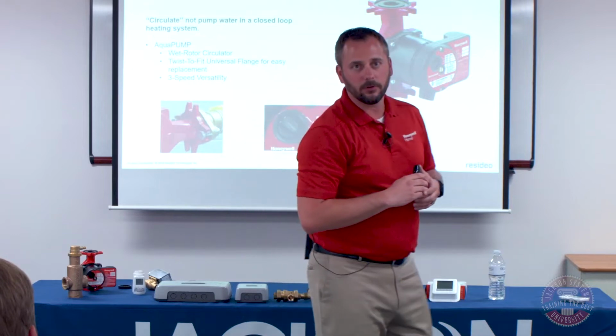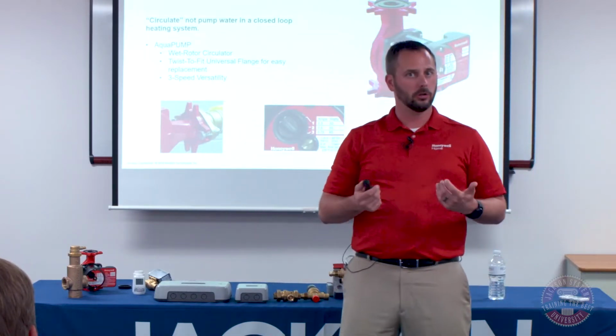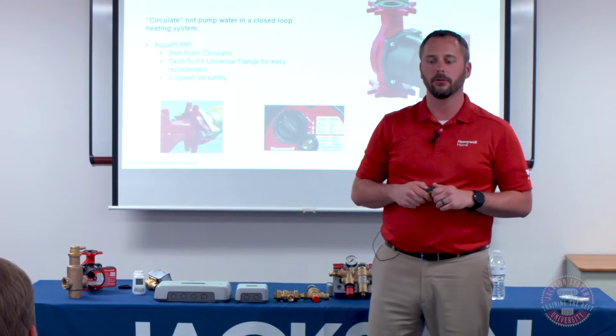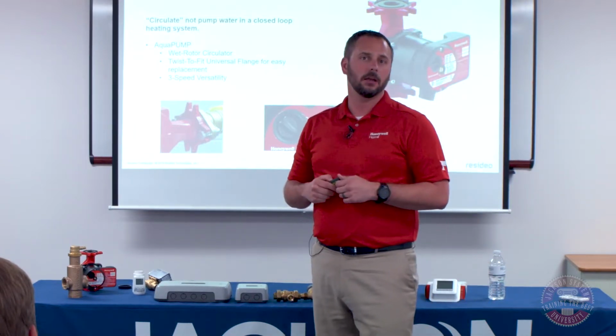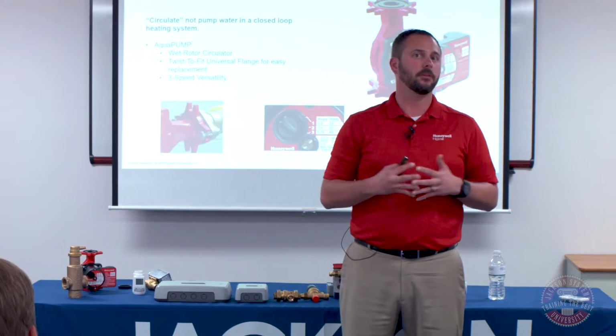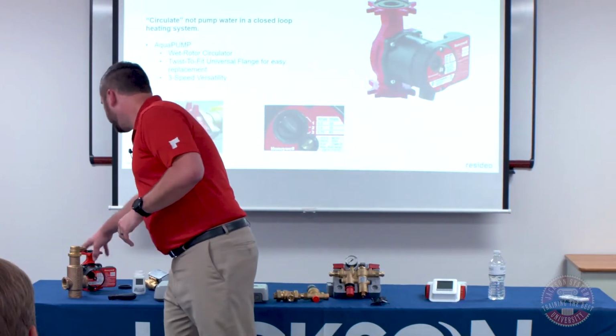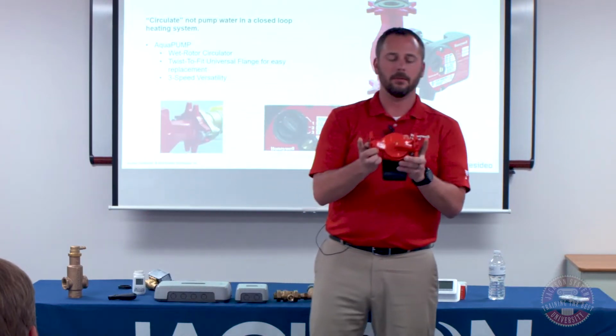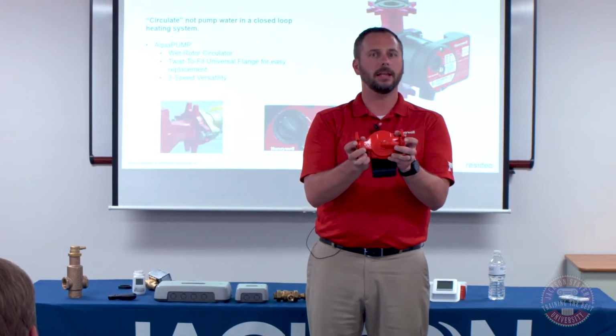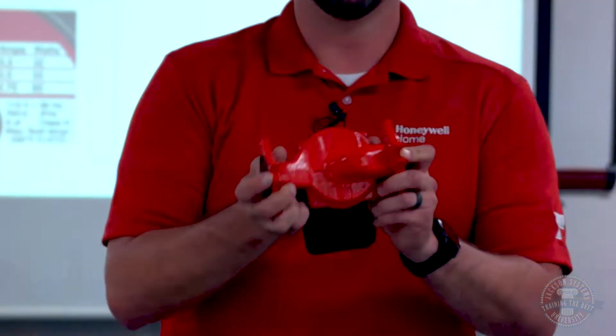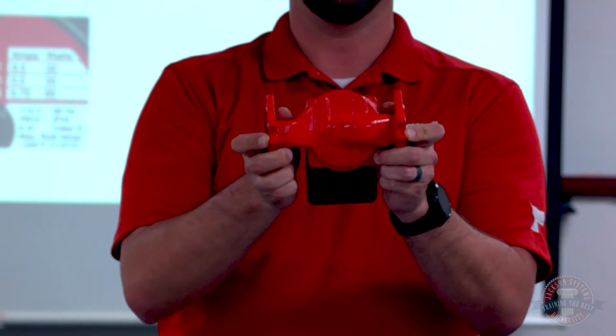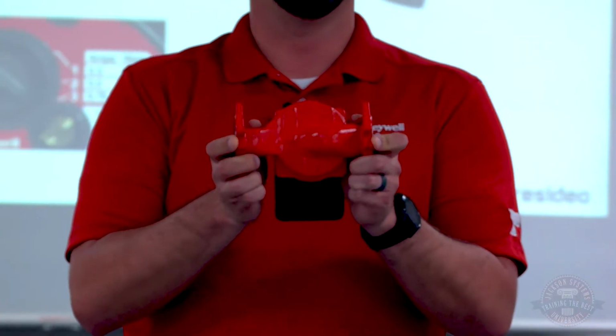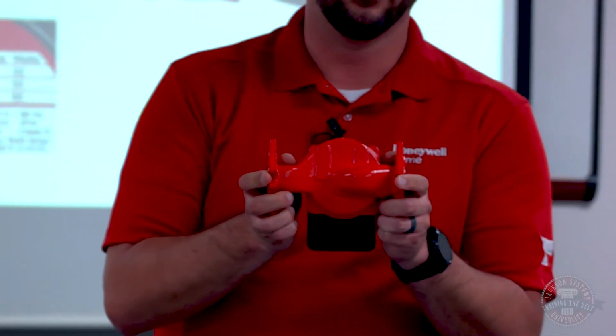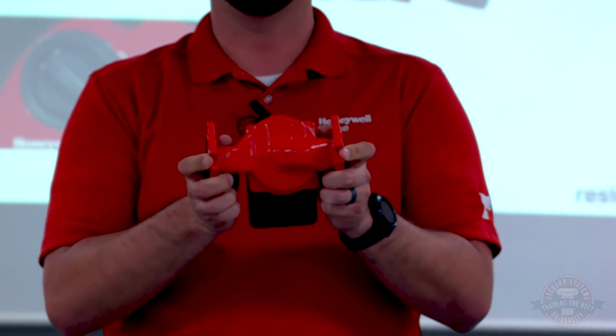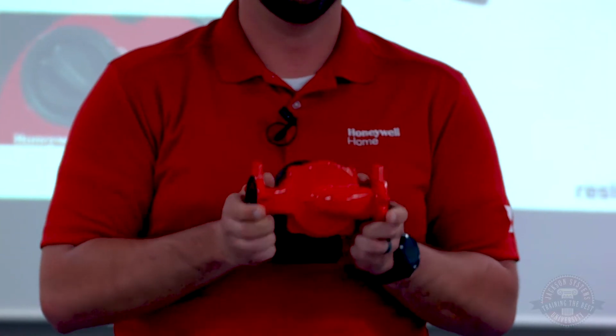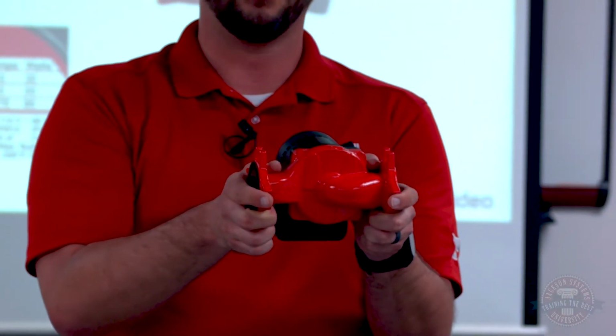We have a couple of pumps in the residential light commercial line that are 3-speed circulators. A couple of things that make this very unique is this is probably one of the best service pumps that's out there. What we've done with it is we have matched it up to the same bolt-to-bolt dimension that you see on anything else in the same horsepower rating. So on our two smaller sizes, it's a 6.5-inch from flange to flange. And on our bigger one, it's 8.5 inches from flange to flange. That is the most common size dimensions that are there. So if you're swapping out a pump, this is going to fit in the exact same spot without having to do anything to the piping.